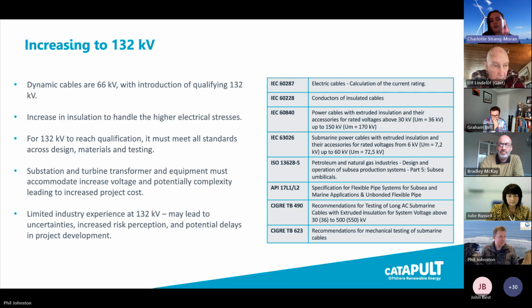Substations, turbine transformers and equipment must be able to accommodate the increased voltage and potential complexity, which may lead to increased project cost for supply, upkeep, and training. Also the increase in connector size for 132 kV. We'll also have a challenge in the supply chain and installation services, where we might need new equipment able to accommodate larger cable due to larger insulation.